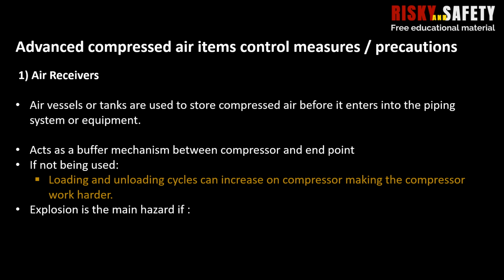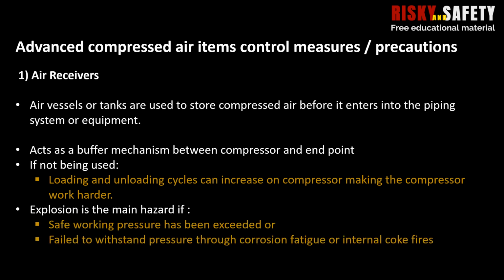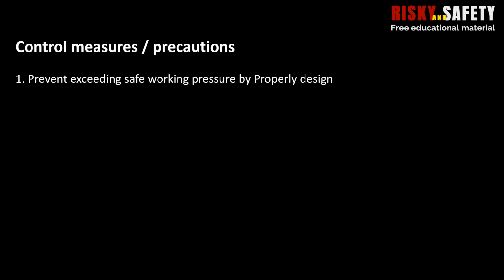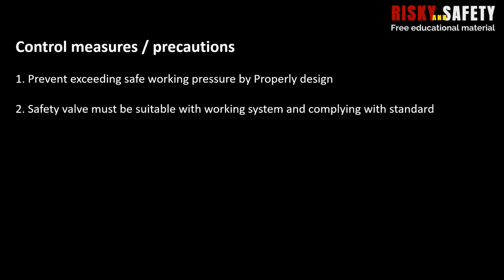Explosion is the main hazard if the safe working pressure has been exceeded, or because of failure to withstand pressure through corrosion, fatigue or internal coke fires. You can control the risks by preventing the safe working pressure from being exceeded, by properly designing and constructing the receiver to withstand the compressor's maximum pressure safely, and by fitting a safety valve and pressure reducing valve.